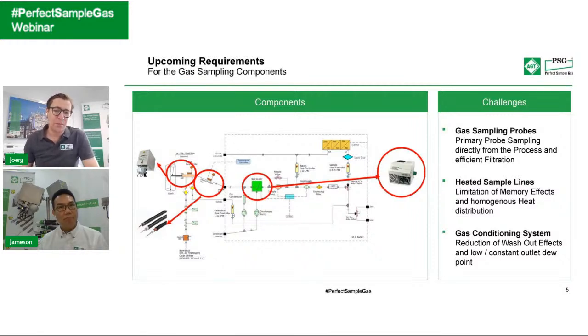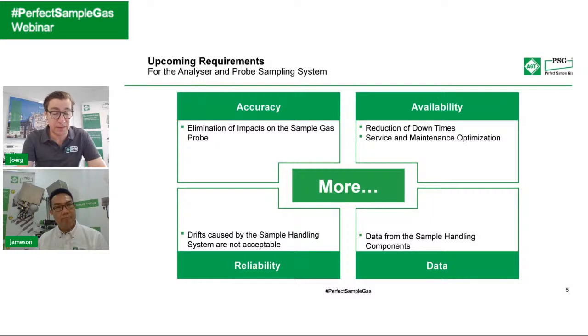So these three typical components, I mean, we like to share this P&ID overview here in our sessions. And you might remember we had the accessory session where we were also talking about filters and other maybe smaller, but very important items inside the sample handling system. So today in the quick fix session, we would like to focus again on the gas sampling probe, the heated sample line, the transportation, and the gas conditioning, especially the gas cooling. Because we will see in the future more requirements that sample handling systems have to be more accurate. The accuracy demand and the availability requirements for the sample handling system will increase in the future. I mean, Jemsen, we've been discussing this in other sessions as well.